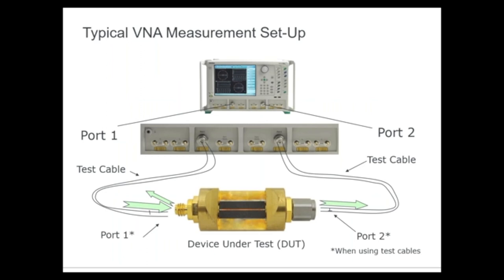In a typical two-port setup, we have a benchtop VNA with port one and port two, test cables attached, and a device under test — here a simple passive device. We're measuring transmission — a signal going from port one to port two — as well as a signal reflecting back at port one and similarly at port two. We measure all signals: transmitted forward and reverse, as well as reflected forward and reverse. In the denominator of our ratio measurement is always what we apply; the numerator is what we measure in reflected or transmitted sense.